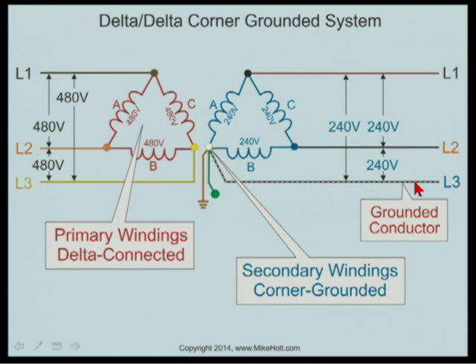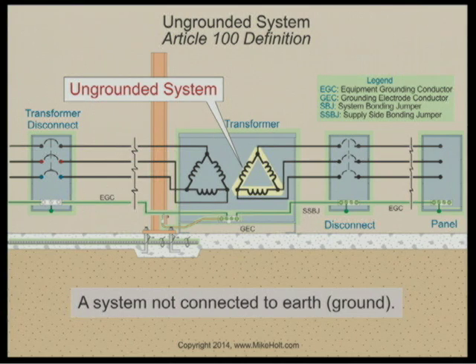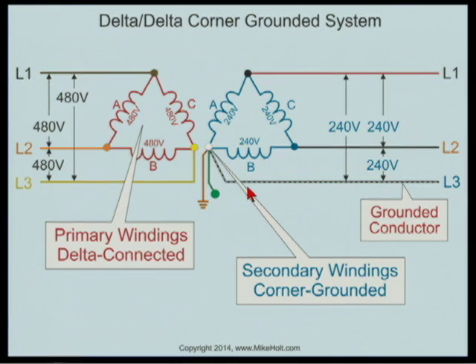So what's the advantage of a corner grounded system? Well, the advantage is this. If we had an ungrounded system, which is permitted by the code because we're not supplying line-to-neutral loads, and everything is going great, but we're finding out, what are we having a problem with on ungrounded systems? Ungrounded systems have a problem of overvoltage, right, Eric? Yep, that's our problem with ungrounded systems. We're like, oh man, what are we going to do? I know what we can do. Let's corner ground one phase, which is fine because we're not supplying line-to-neutral loads. We're supplying line-to-line loads.